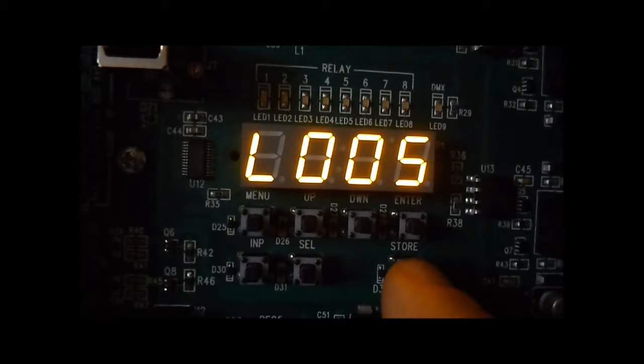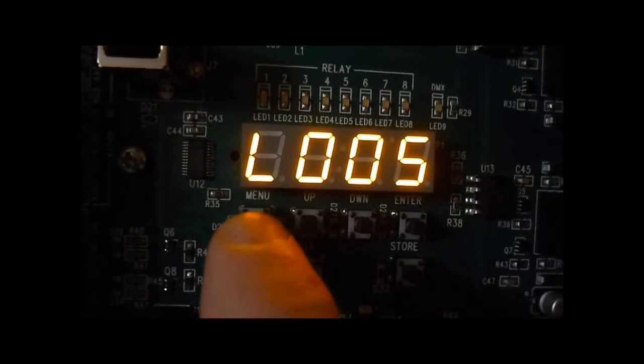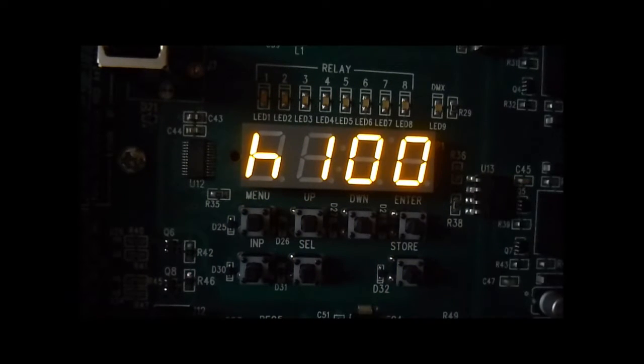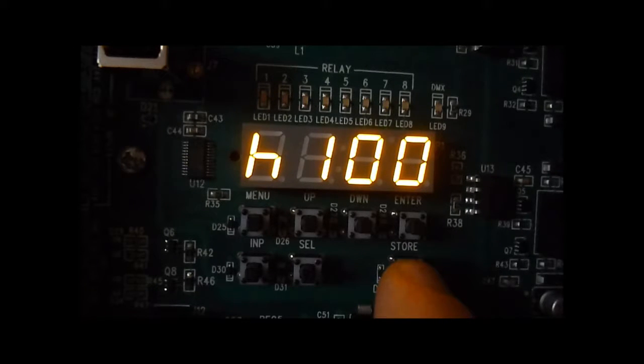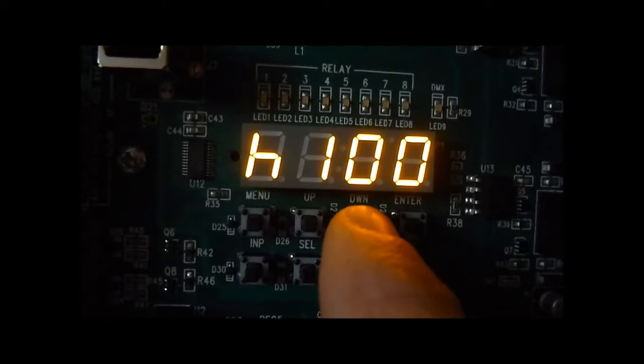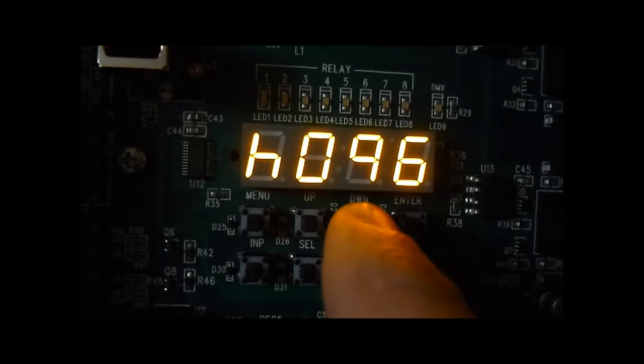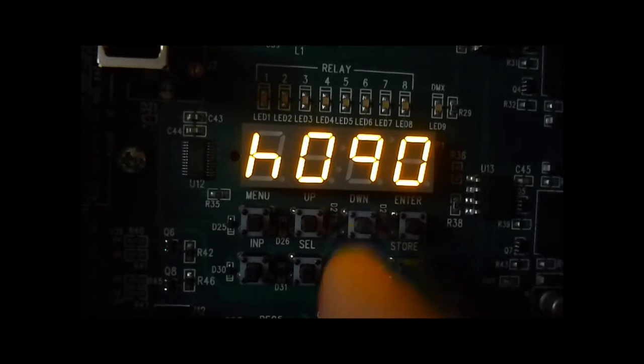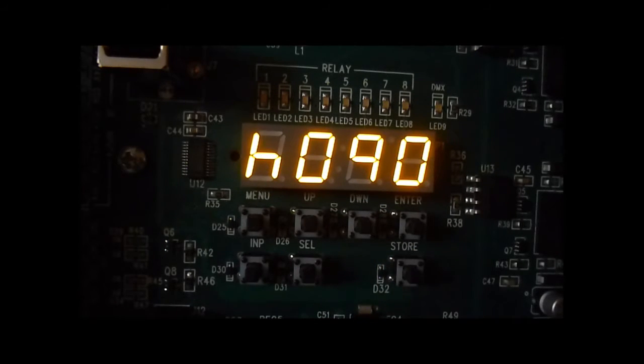Press store, back out, and select the high trim. This becomes the maximum value on the range from low trim to high trim. This typically defaults to 100%, but if you want to reduce the maximum value on a 0 to 10 volt dimming output, you can pull that back, say to 90%, and then just press store.